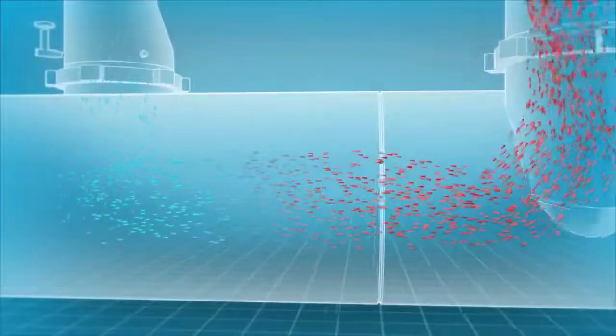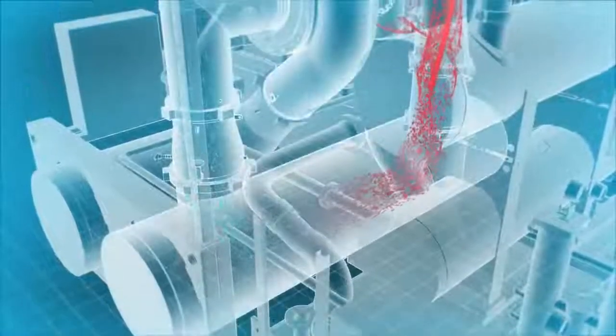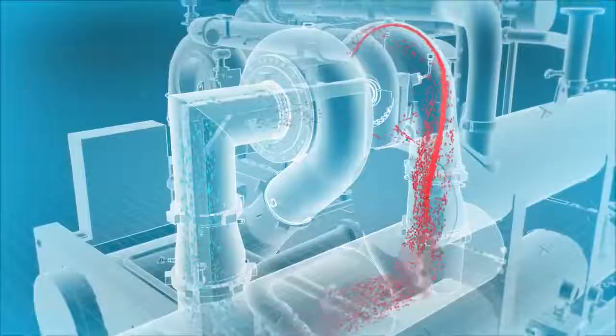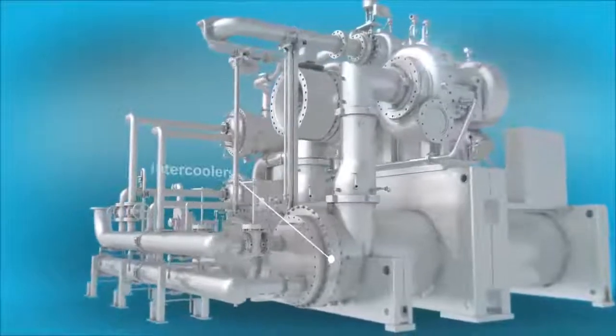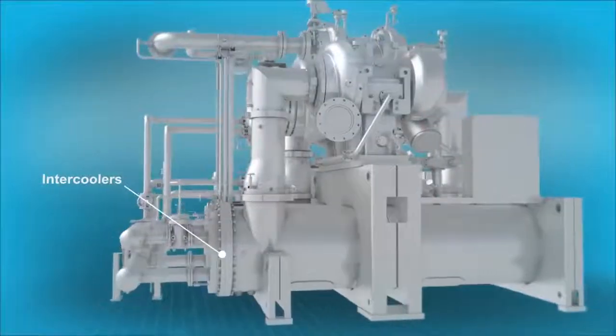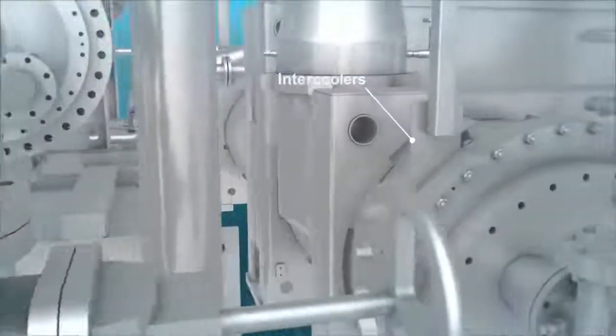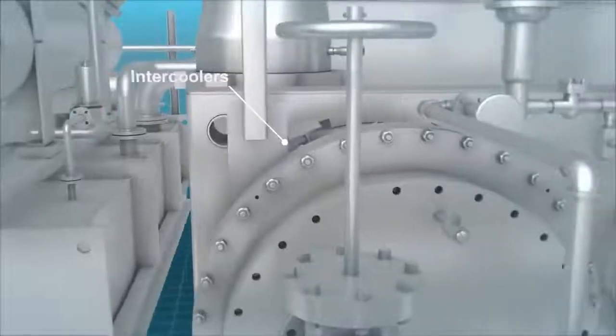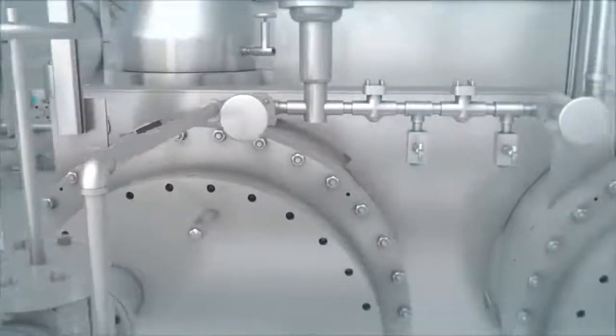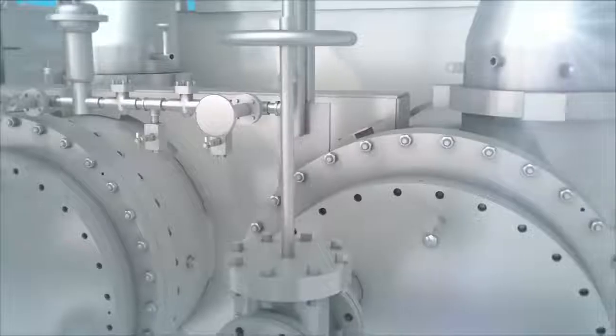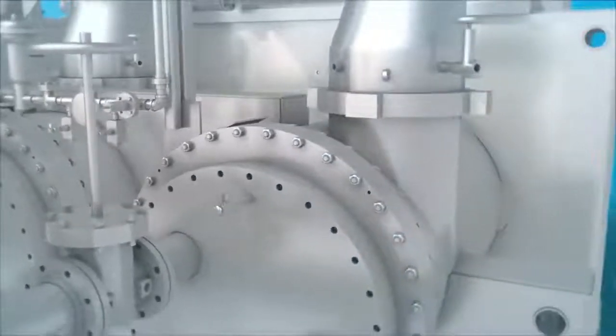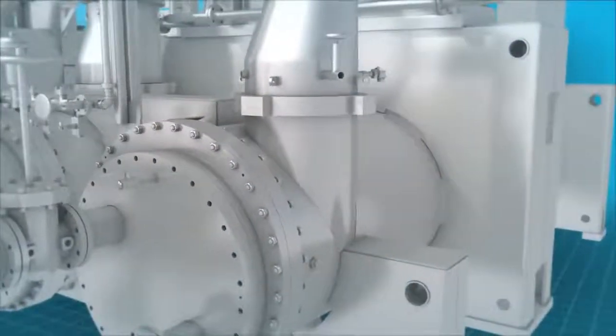Gas temperature rises during the compression process. To improve compression efficiency, interstage cooling can be easily accommodated between any of the compressor stages. Atlas Copco offers a range of intercoolers that are precisely matched to process requirements and meet all relevant international standards. In the configuration shown, water coolers are available in either water-in-the-shell, gas-in-the-tube, or gas-in-the-shell, water-in-the-tube designs.